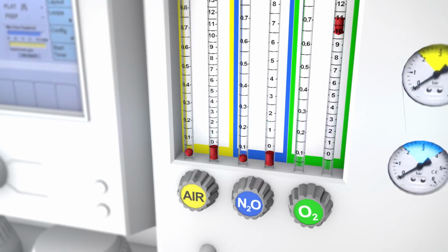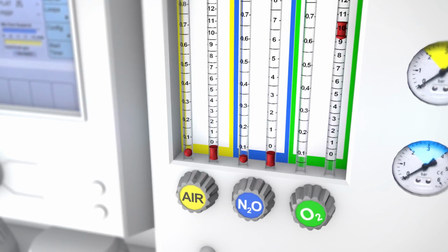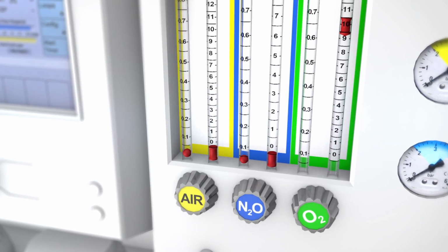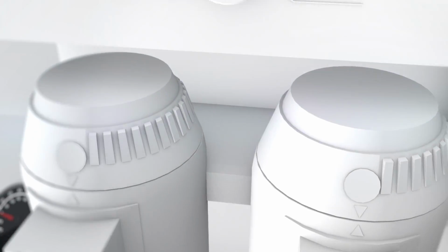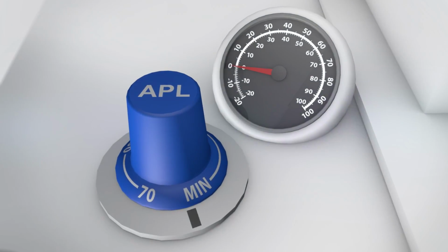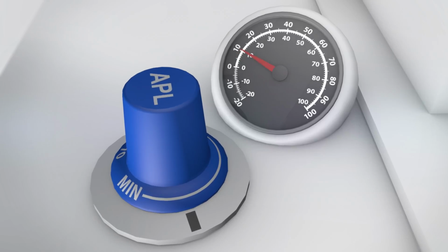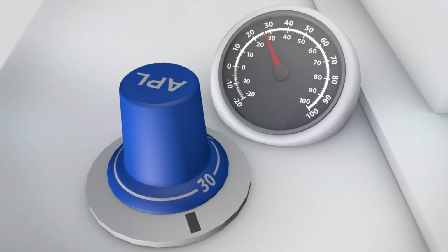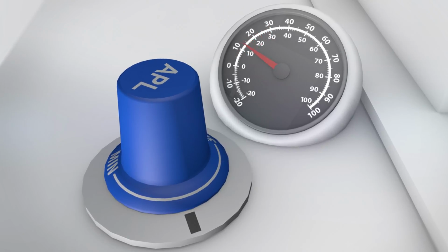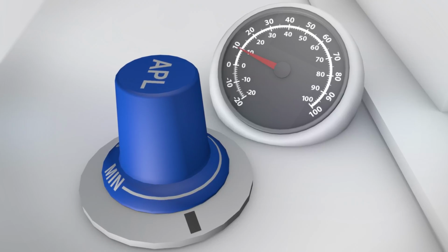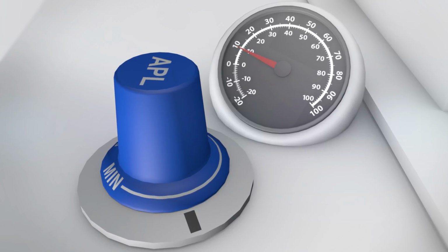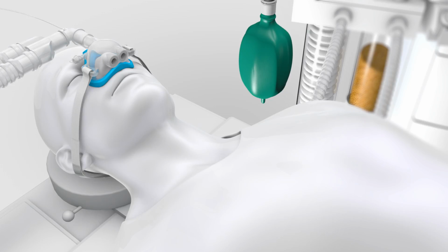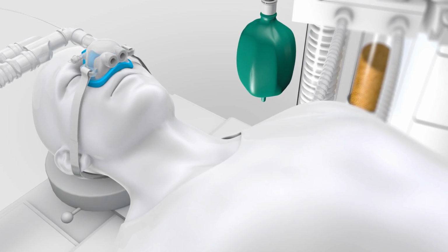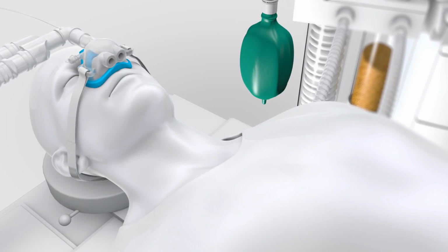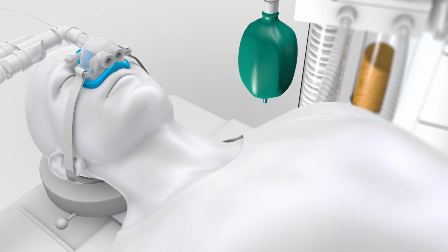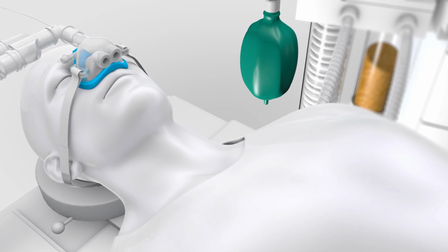Initially, high fresh gas flows are necessary to quickly fill the reservoir bag and allow for positive pressure generation. Use the adjustable pressure limiting valve to limit and set the amount of pressure buildup that occurs. Titrate fresh gas flows and the adjustable pressure limiting valve settings as needed to maintain upper airway patency and allow for ventilatory support. With the SuperNO2VA device properly sealed on the patient's face and fresh gas flows set at a rate higher than minute ventilation, the reservoir bag will fill and pressurize.